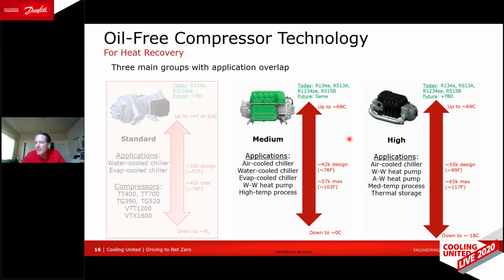For that industrial process, similar to a data center but at a slightly lower cooling temperature, the optimal solution was medium pressure optimized compressor designs for the low stage of a series counterflow arrangement of chillers and heat pumps, and then high lift compressors designed for the high stage, optimized for that operation and the generation of heat on the high stage.